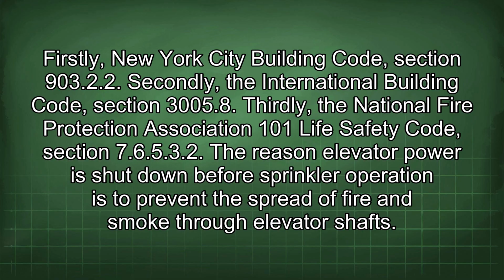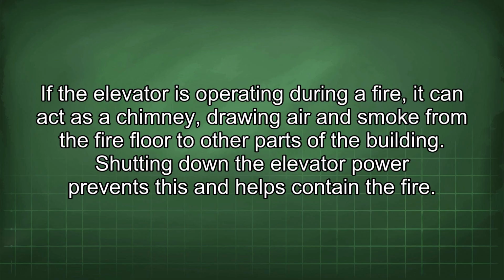through elevator shafts. If the elevator is operating during a fire, it can act as a chimney, drawing air and smoke from the fire floor to other parts of the building. Shutting down the elevator power prevents this and helps contain the fire.